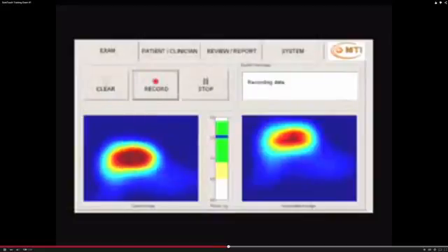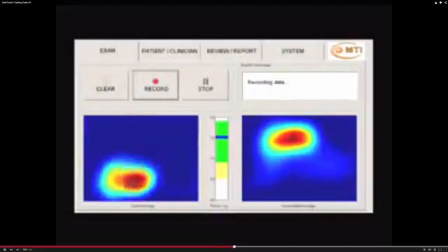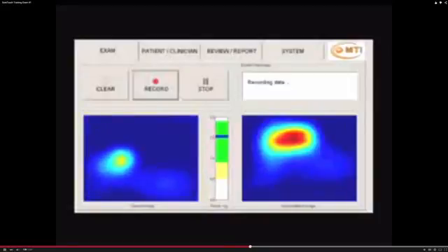Notice that we now have image data appearing on the accumulated image field on the right side of the interface screen. The accumulated image is generated automatically once we've begun to probe the area above the suspicious lesion with sufficient force. Note that the SureTouch system is configured to accumulate images anywhere from 0.6 through 2.4 kilograms of total load applied to the probe, depending on the patient's breast size, density, lesion size, and depth.